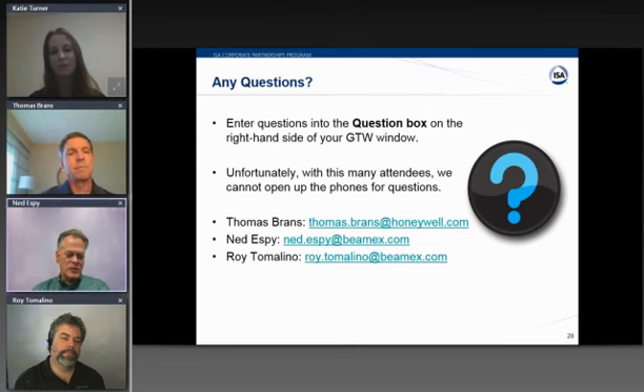Well, if you look at our brochure for the MC6 that Roy was demonstrating today, we state uncertainty in our specifications, and we use a K factor of 2. So we state a one-year stability with a 95% confidence level, and our statement includes the reference standard as well as hysteresis, nonlinearity, and other components. So we state a very conservative number. I would say just go to beamex.com and you can look at those numbers.